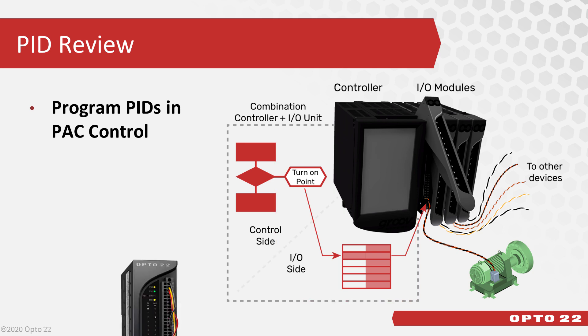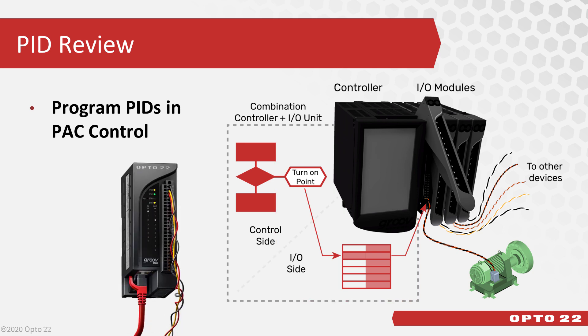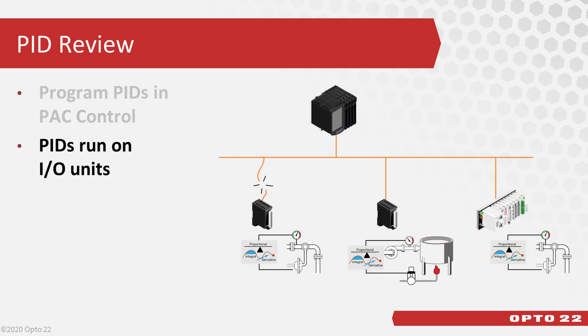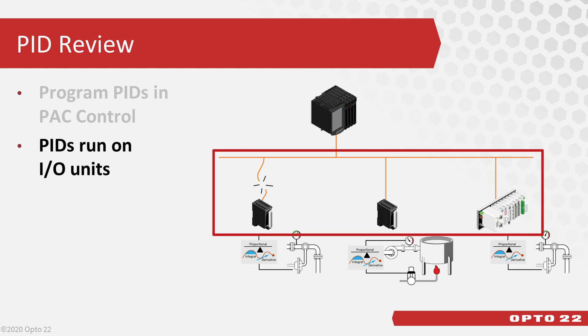If your strategy uses a remote IO unit, such as a groov RIO, then commands for points on that unit are executed by its own processor. The PIDs configured in PAC Control actually run on the IO unit side, independently of the controller.